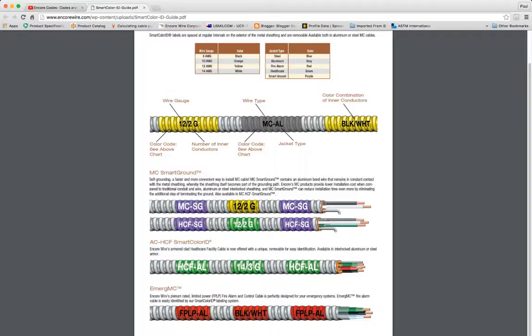But we will provide them for you in case it helps you out on your job or somebody might not be as knowledgeable and you end up being told you have to have them. If you have that problem, always feel free to contact us at codes at EncoreWire.com. We're more than happy to get involved and explain that MC cable doesn't need anti-short bushings. It's designed into the fitting, but some people get confused with that.